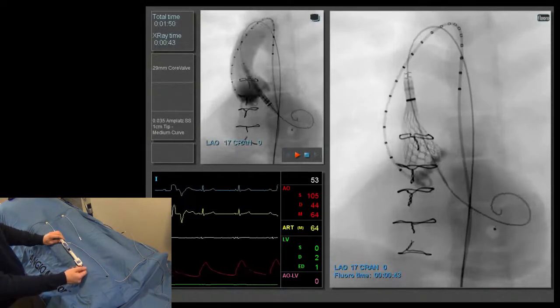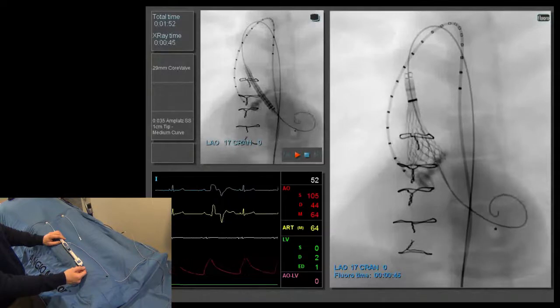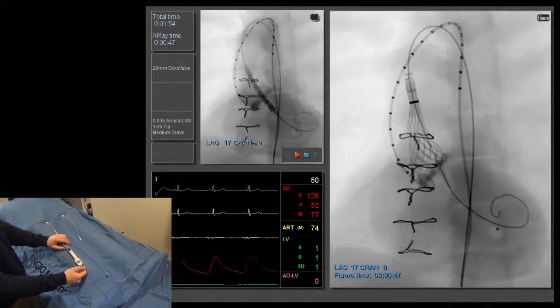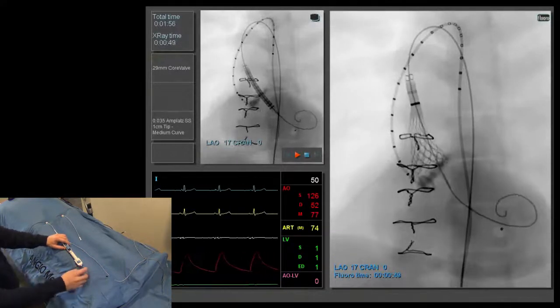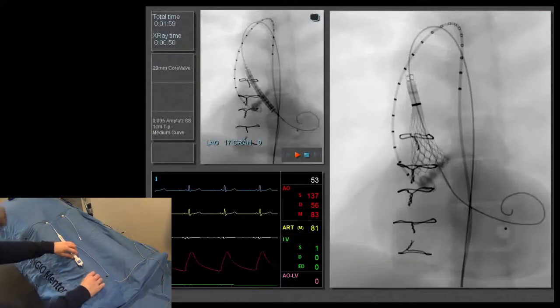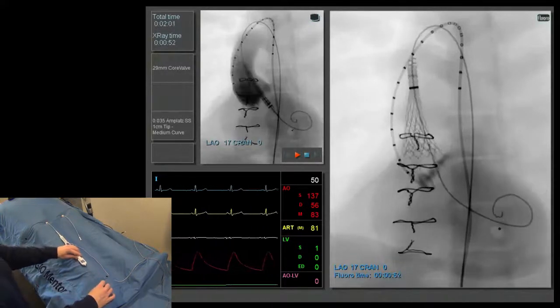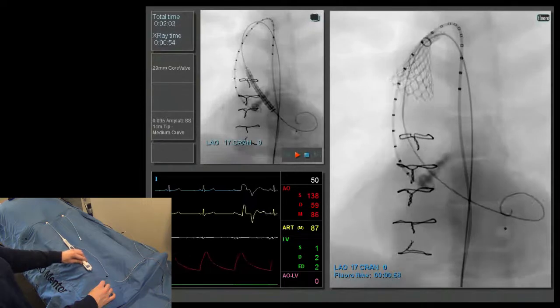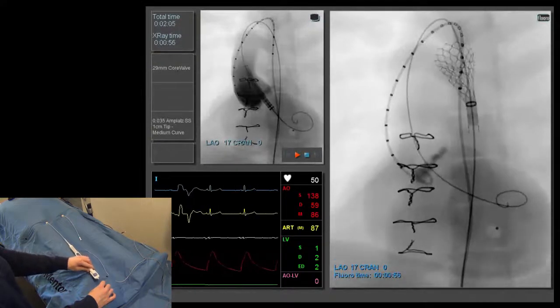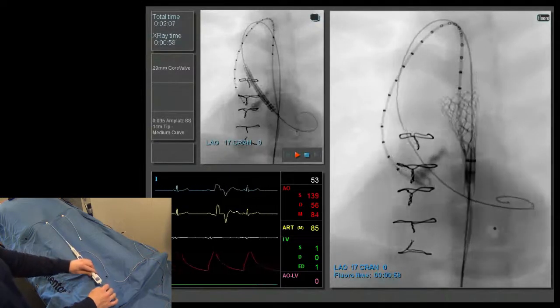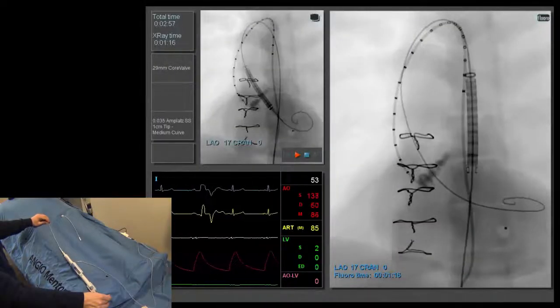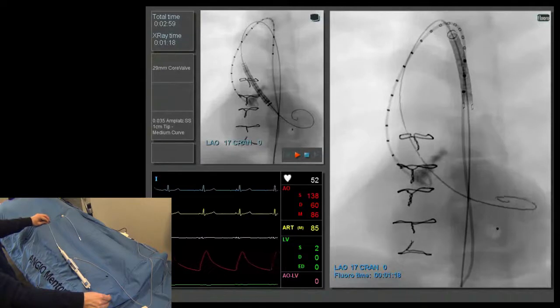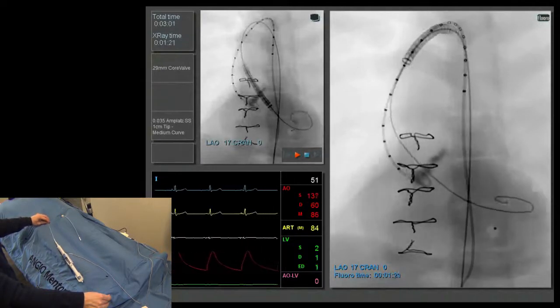And this is almost towards the point of no return. And for this reason or another, maybe one forceful beat, VPB, there is a pop out of the prosthesis. Now, with the new Evolut system, the valve can actually be recaptured. With the first generation, as you can see here, it needs to be retrieved back to the sheath, and a new valve is immediately introduced.